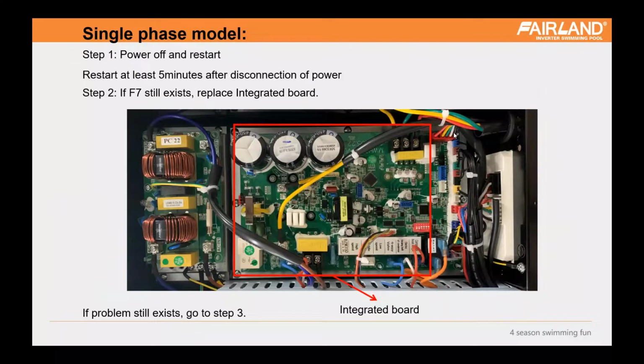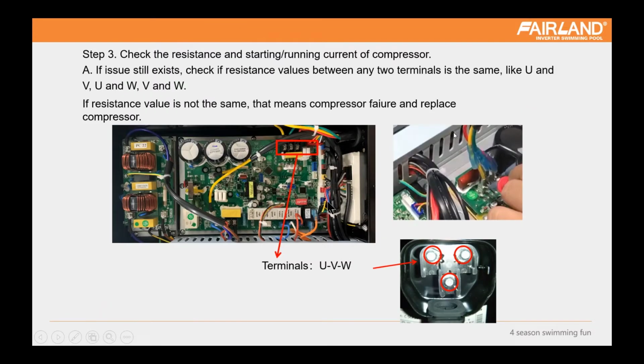If reset is not workable, then we will replace the integrated board for this one, and do the same detection on the compressor to make sure the compressor is fine. Normally, the problem comes from the integrated board.